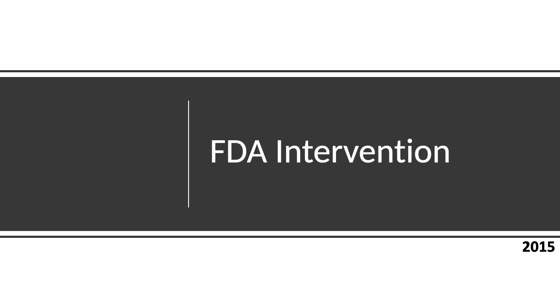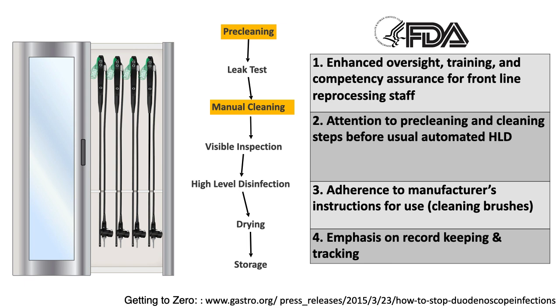So, although we know all these things, why did FDA intervene? Because FDA felt that there were several problems related to scope-related infections, and they came up with these recommendations. One, there should be enhanced oversight, training, and competency assurance for the frontline reprocessing staff. Next, there should be proper attention given to pre-cleaning and cleaning steps before the usual automated high-level disinfection. One should adhere to the manufacturer's instructions for use. And finally, good record keeping is essential to track any scope-related infection. It's almost like tracing for a COVID case. So similar to that, unless you keep records, nothing is going to happen.